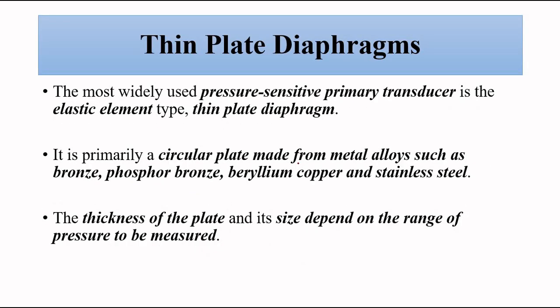The commonly used metallic alloys are bronze, phosphor bronze, beryllium copper, stainless steel. As I said, the thin plate diaphragms are made of special metallic alloys, which are bronze, phosphor bronze, beryllium copper and stainless steel. And the choice of the material, its shape, its size, the dimensions, depend on the magnitude of the pressure, the range of pressure which is to be measured. That determines the choice of material, the size, the shape. It is circular, but the radius and all that depends on this.